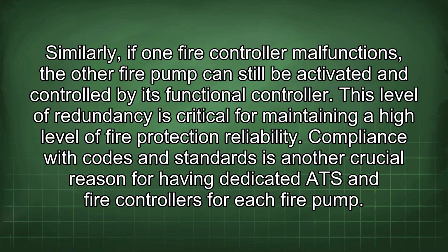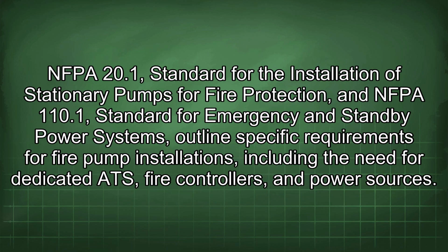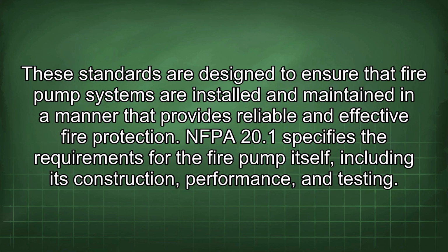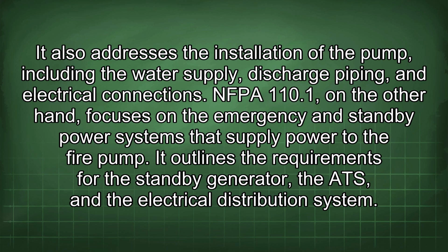Compliance with codes and standards is another crucial reason for having dedicated ATS and fire controllers for each fire pump. NFPA 20.1 standard for the installation of stationary pumps for fire protection, and NFPA 110.1 standard for emergency and standby power systems outline specific requirements for fire pump installations, including the need for dedicated ATS, fire controllers, and power sources. These standards are designed to ensure that fire pump systems are installed and maintained in a manner that provides reliable and effective fire protection. NFPA 20.1 specifies the requirements for the fire pump itself, including its construction, performance, and testing. It also addresses the installation of the pump, including the water supply, discharge piping, and electrical connections.